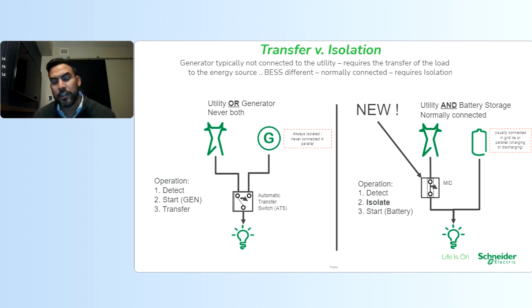Why is it different for a battery energy storage system? Well, primarily battery energy storage systems are grid connected devices, different than a generator. There's a lot of use cases that come with the battery energy storage system, and I'll highlight those in the next slide. Whether it's time of use management or self-consumption, the utility's present for at least like 99% of the time. And then when we lose power, we want to enable that energy storage system as an added use case to provide resiliency to those critical loads in your infrastructure, rather than have that energy system just sit in the dark without any functional use. And that's where the automatic interconnection switch comes in here to truly disconnect, and is designed and UL listed specifically for this application.